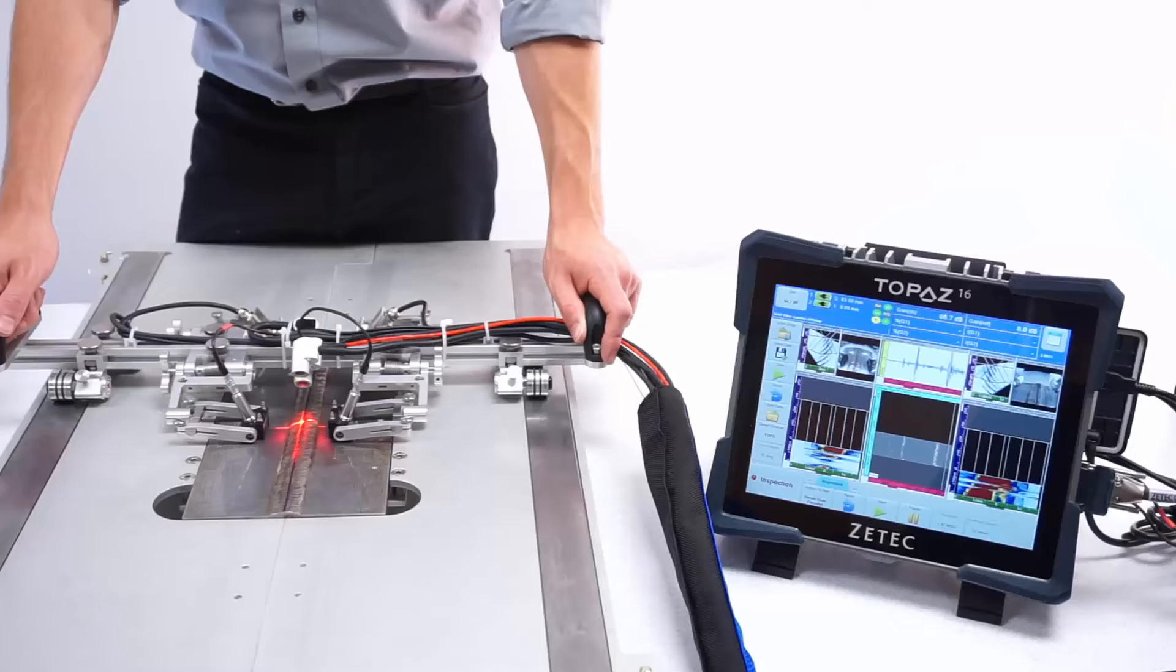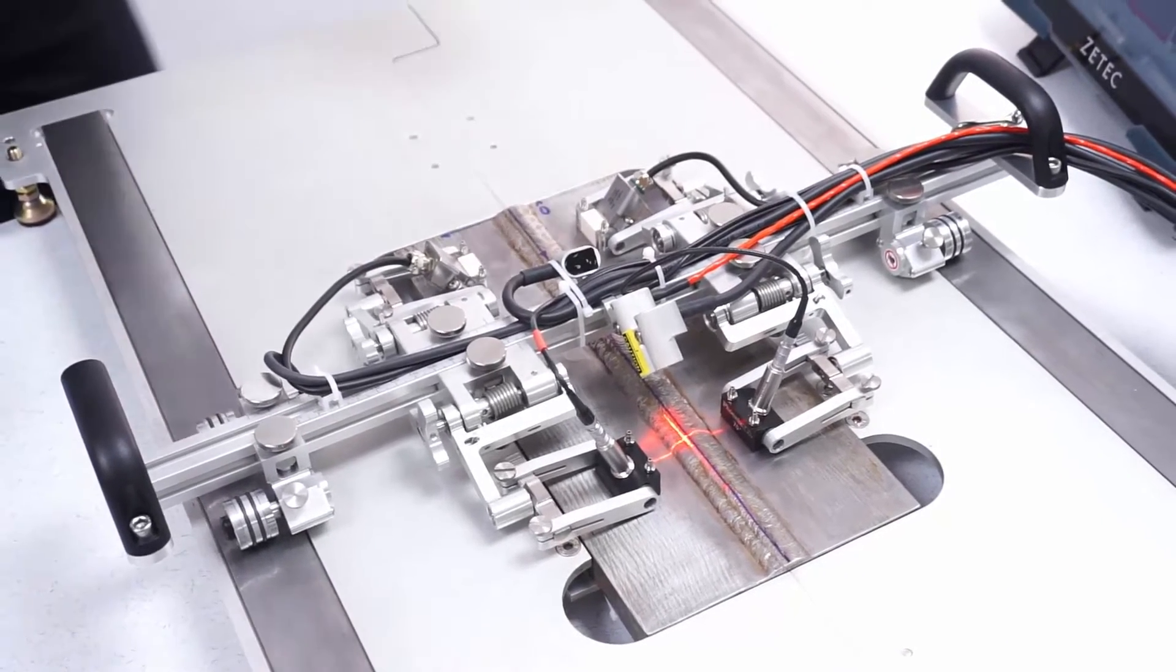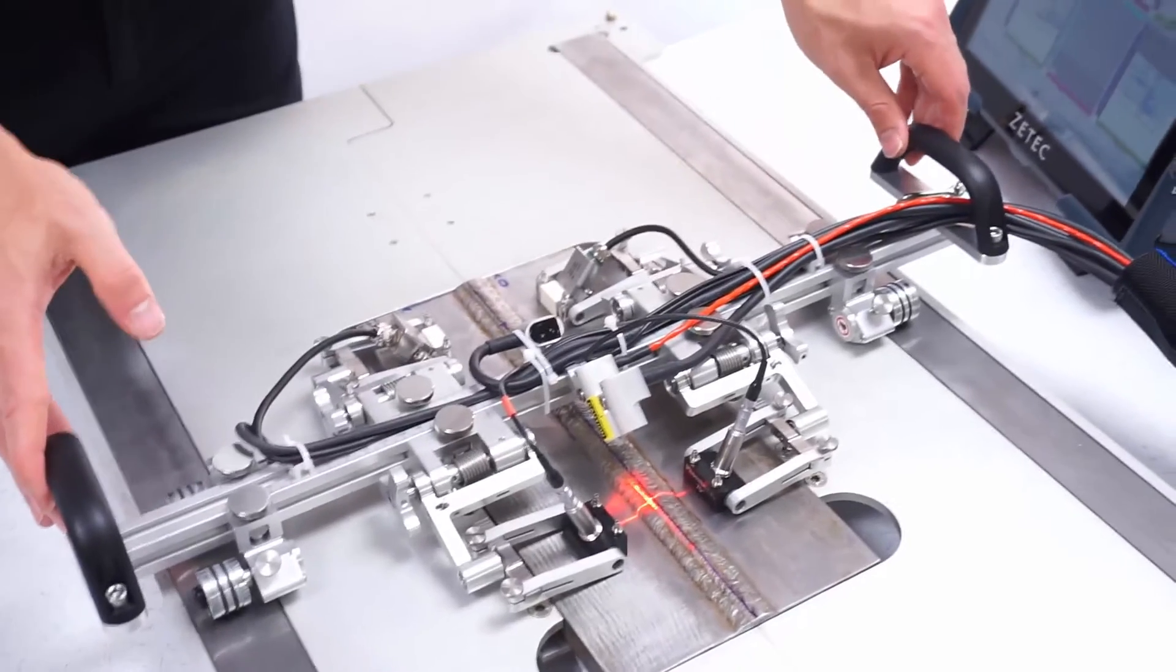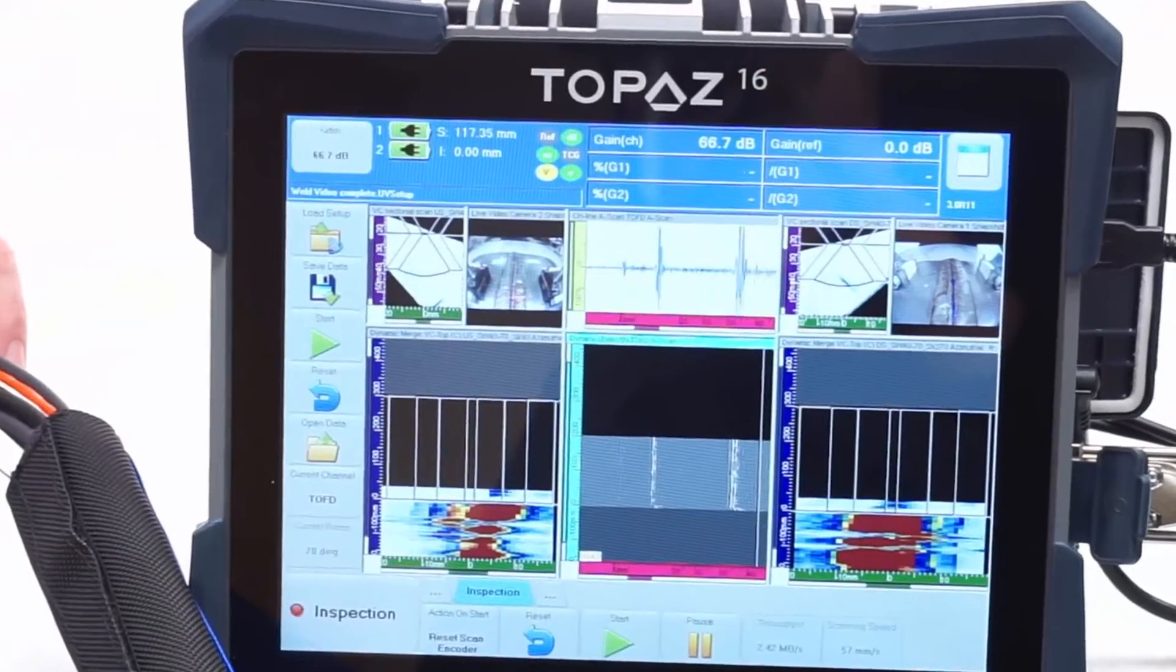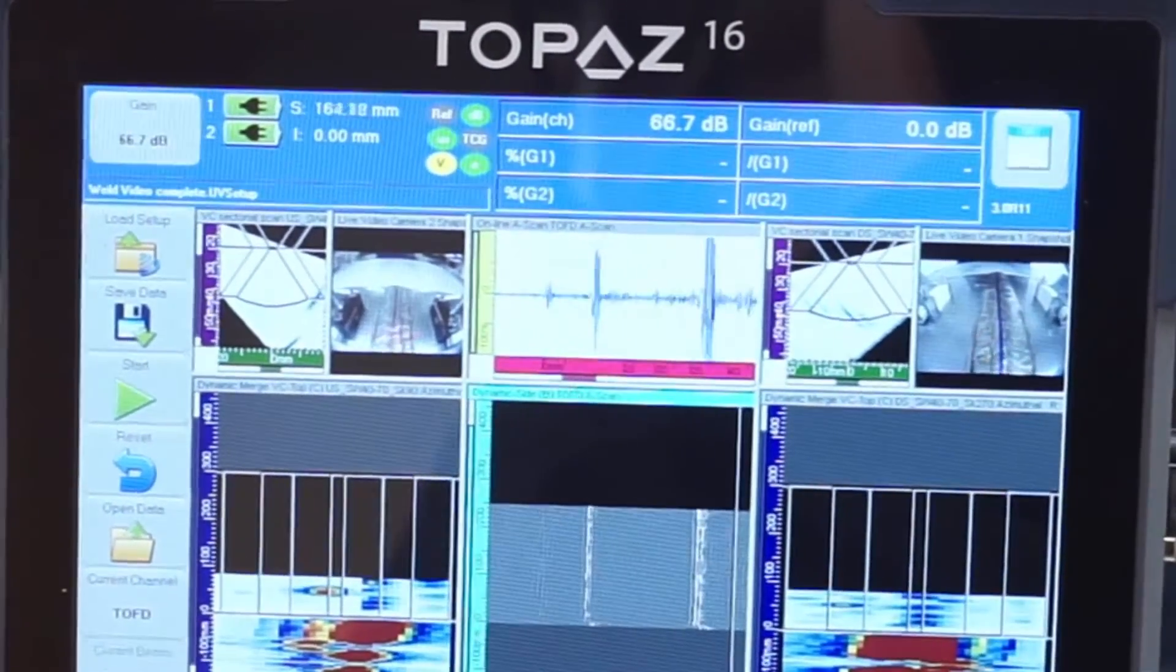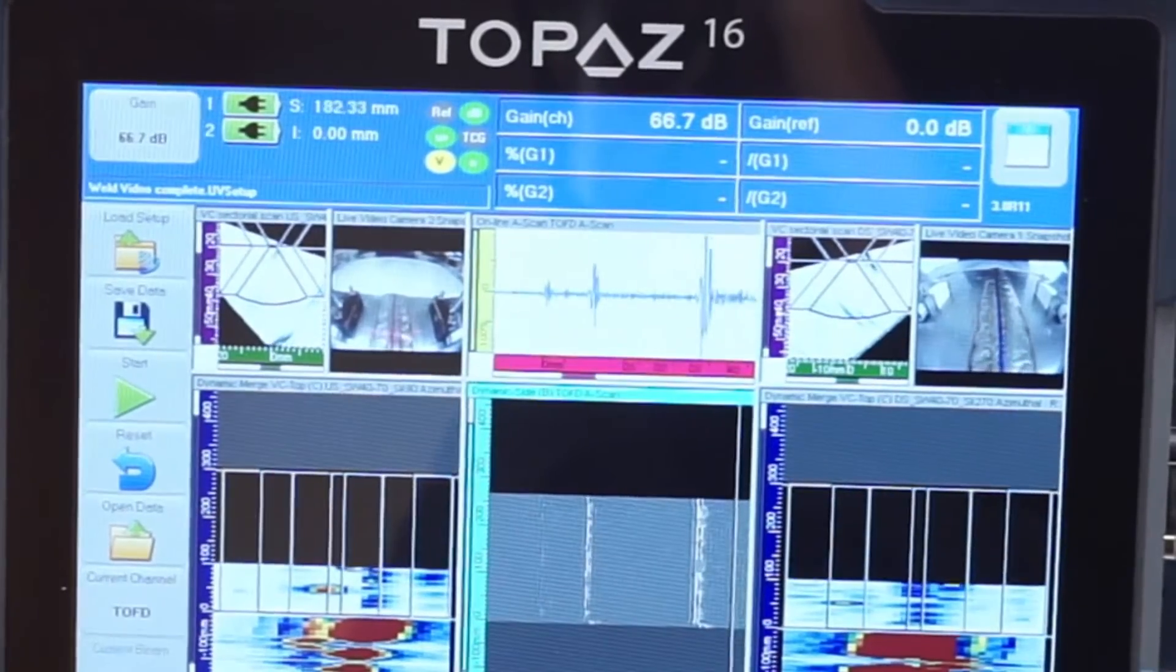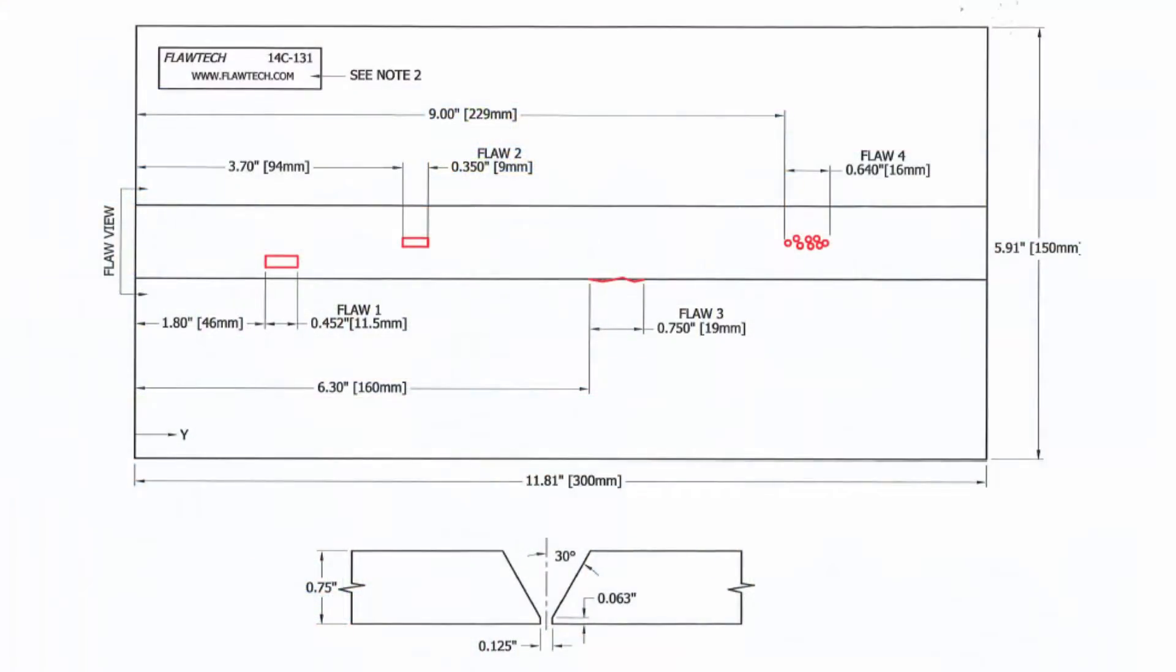The cameras are extremely useful for monitoring the coupling of the probes on the component surface and potential drifting of the scanner from the weld centerline. The video images can be displayed on the TOPAZ screen during data acquisition and can be saved with the ultrasonic data to provide additional information during data analysis.